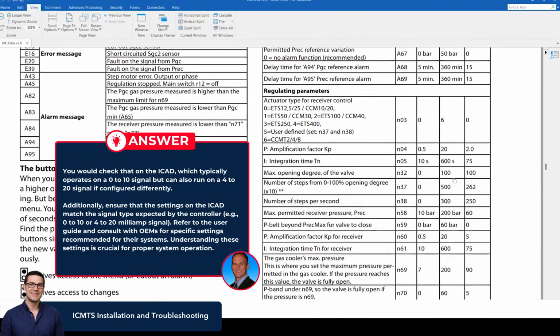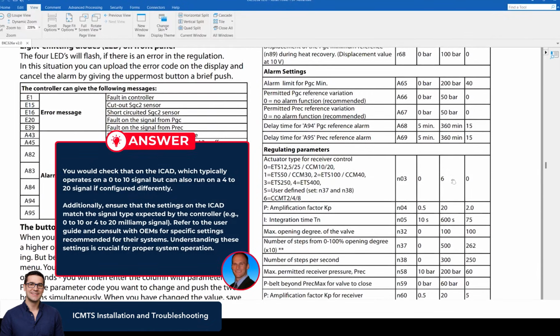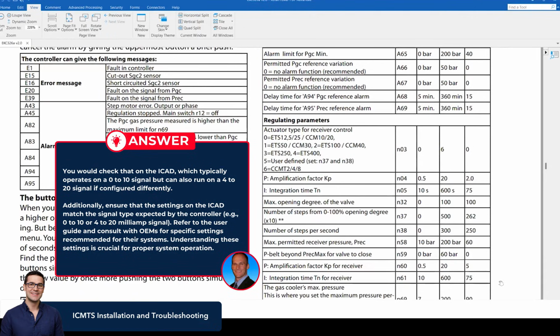But there's settings that say, are we expecting on the ICAD side a 0 to 10 or a 4 to 20? So if you're using an EKC 326, for example, where the 0 to 10 is the only option, but the ICAD is set to expect a 4 to 20 milliamp signal, then that's obviously not matching up. And that's where we need to focus on changing that setting in the ICAD so that they do. Things like that, when you really look at the EKC and on the OEM side, understand what a lot of these settings should be. Because for us, we're not necessarily going to know.